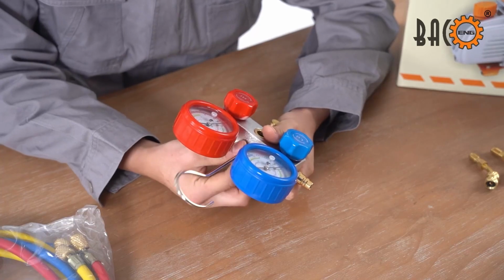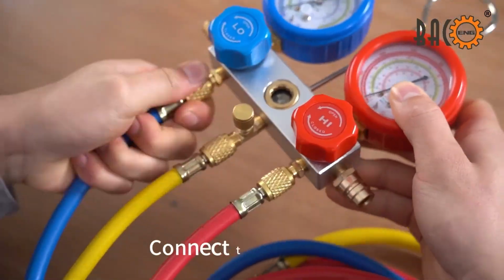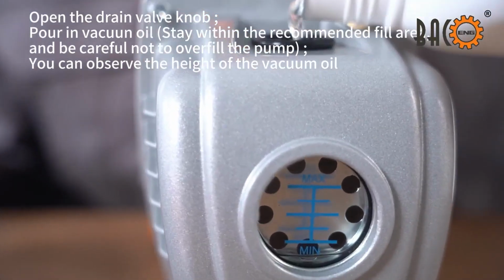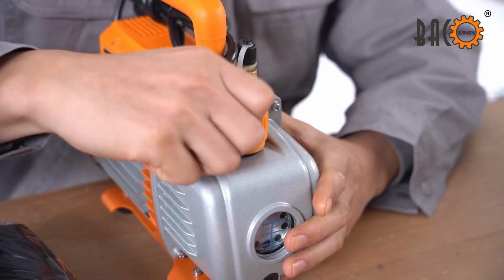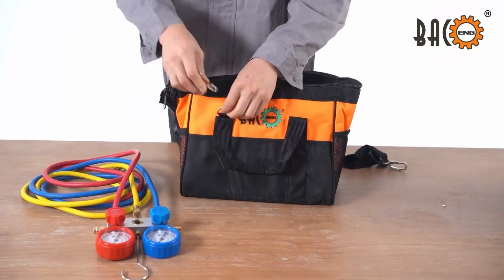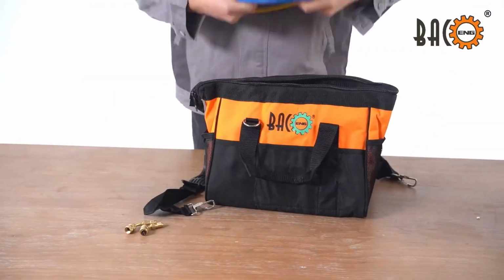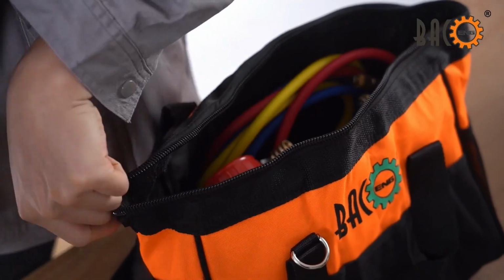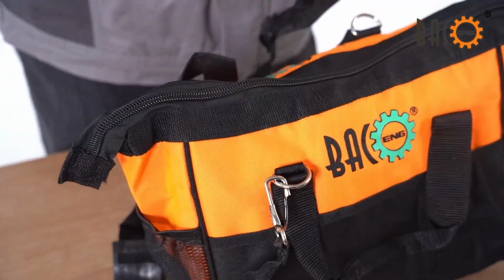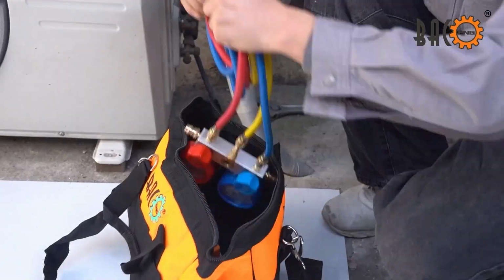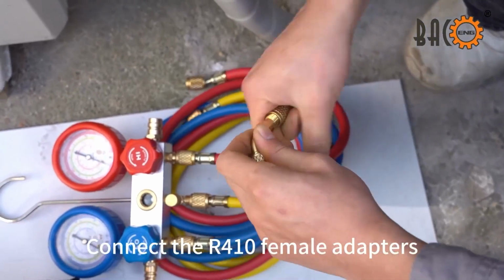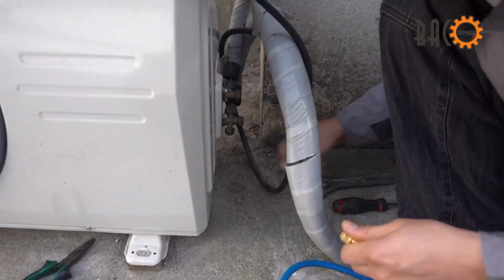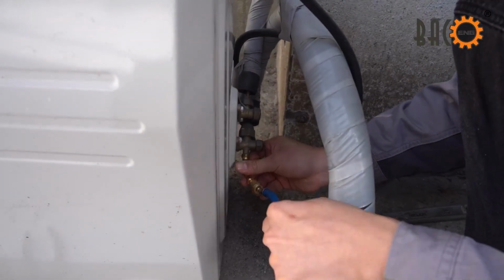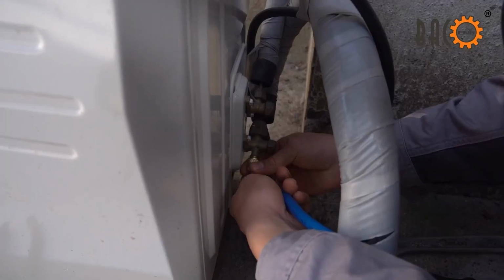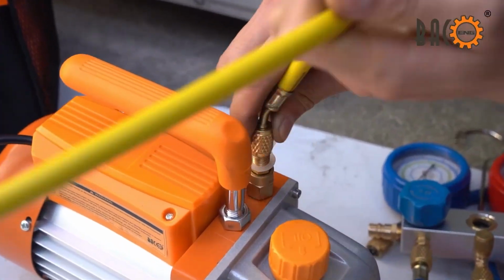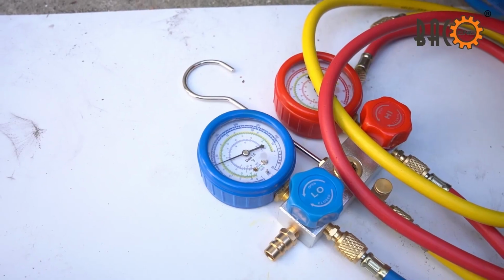No service is complete without a deep vacuum. The BACOENG 3.6 CFM vacuum pump and gauge set is engineered for mini-split perfection, reaching an ultimate vacuum of 0.8 Pascal. The kit includes the pump, the three-way manifold, and R410A adapters. A proper deep vacuum is non-negotiable. It removes moisture and non-condensables, guaranteeing system longevity. This kit is the perfect balance of power and portability for residential installers.